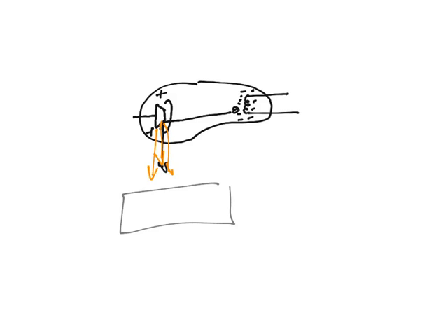And so you increase the voltage. Higher voltage, you're attracting the electrons harder, they move faster, and thus when they stop, because they hit the anode, the X-rays which are produced are much more highly energetic. And of course, if you want to get a faster image, or you need to have more light, quote unquote, shining onto the film, you can increase the current to make more electrons go through per second.